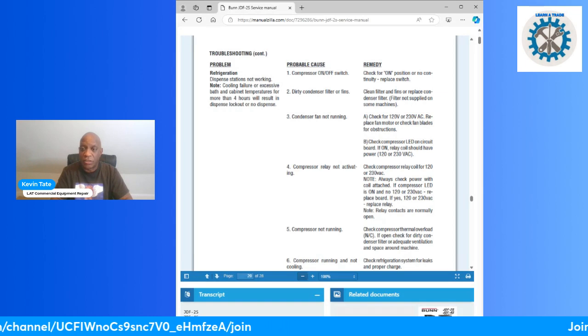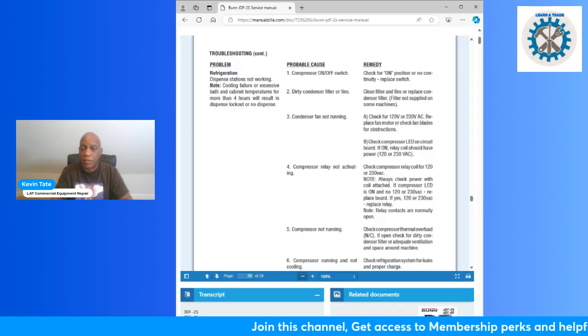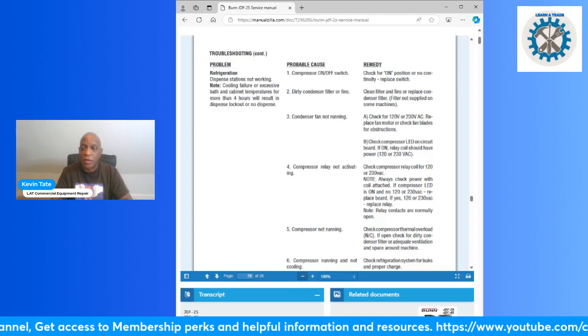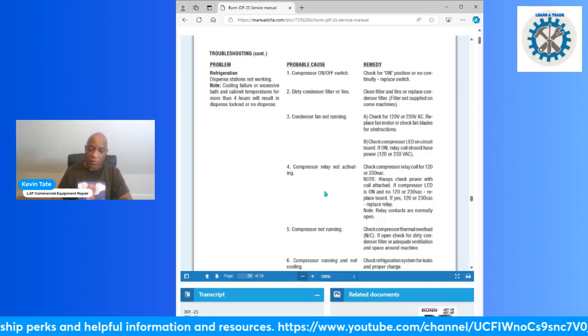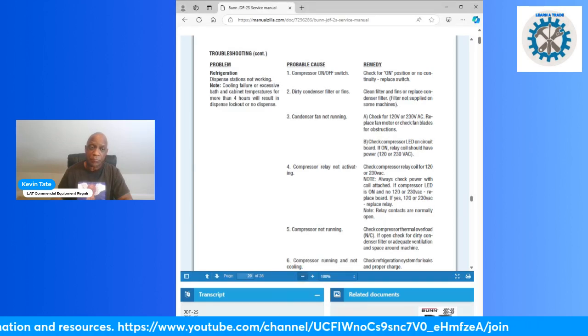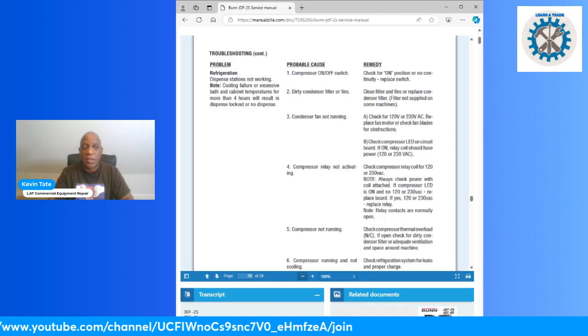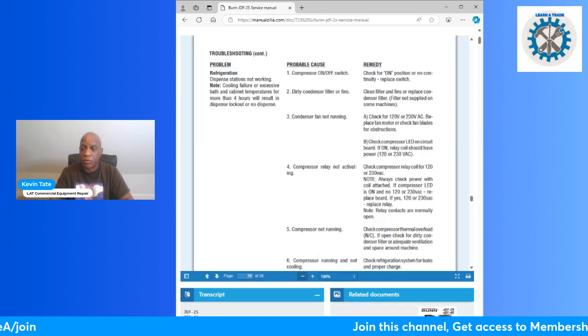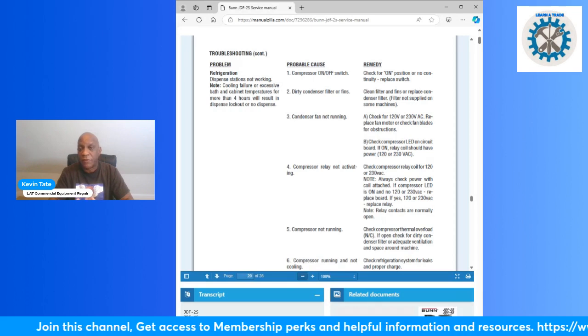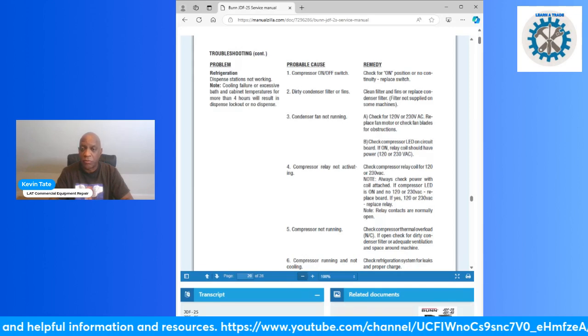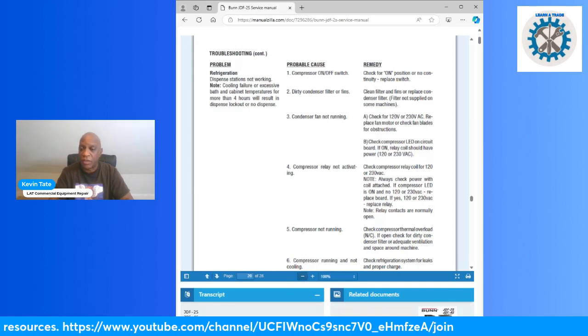Another thing is a dirty condenser filter or fins, which can cause some refrigeration issues. The condenser fan may not be running, so you'll want to check into that. If it isn't running, I would advise that you get your multimeter and take a look at the voltage. Make sure you have the 120 volts or 230, whatever you're working with there. Make sure you have the voltage going to that fan motor. But you definitely want to make sure that the condenser fan is running.